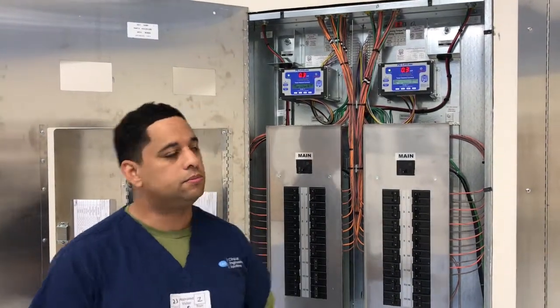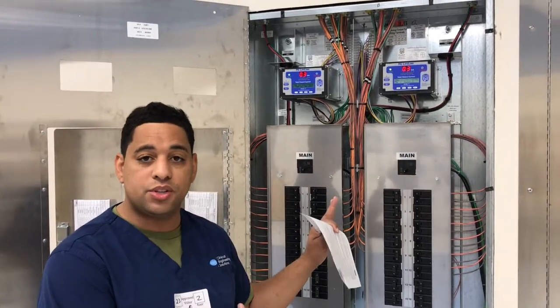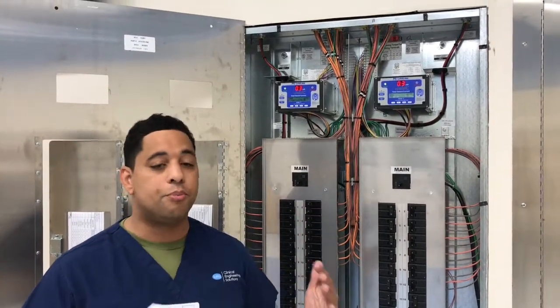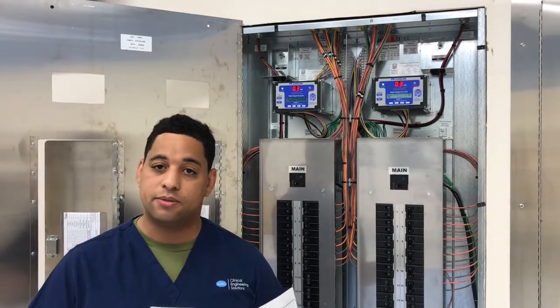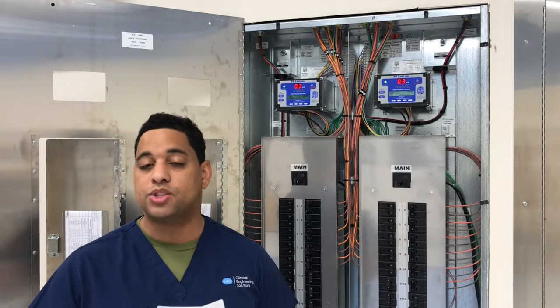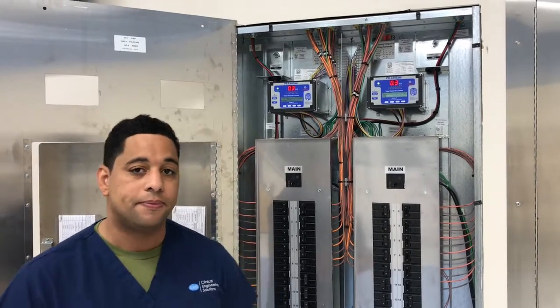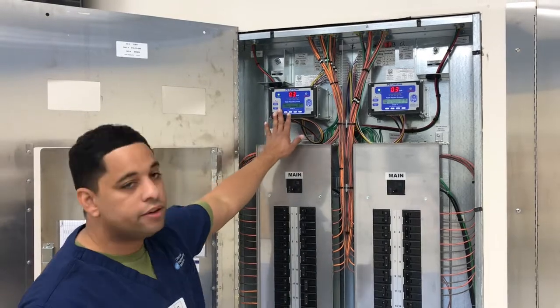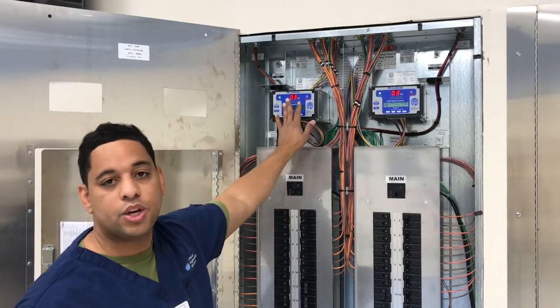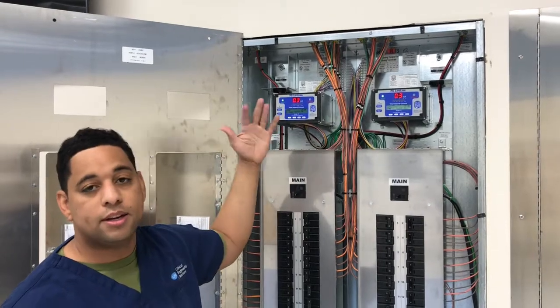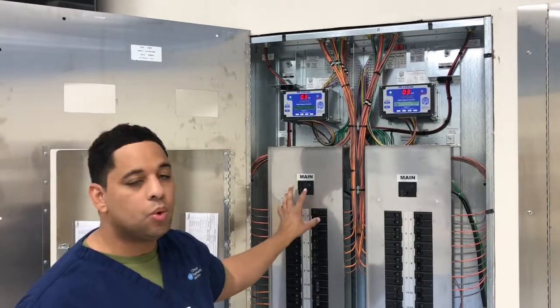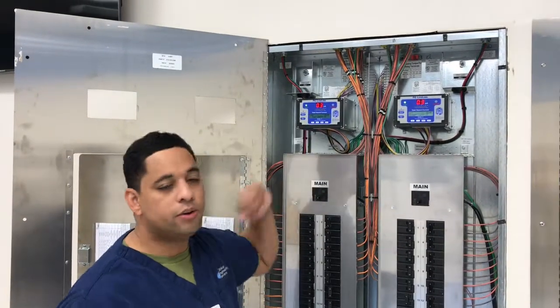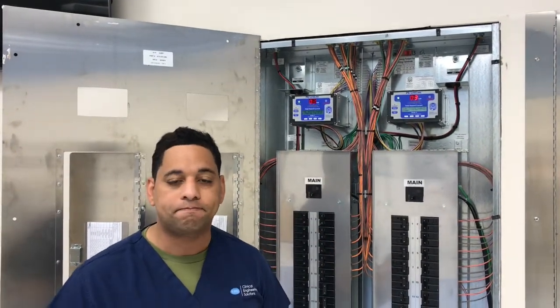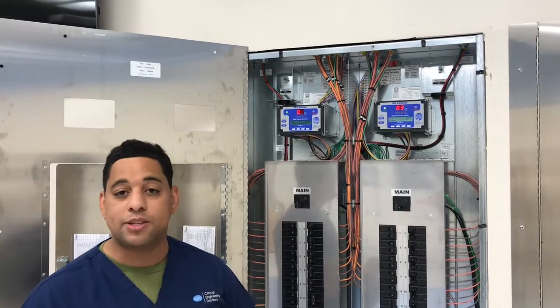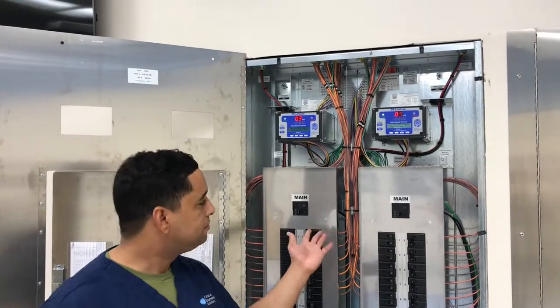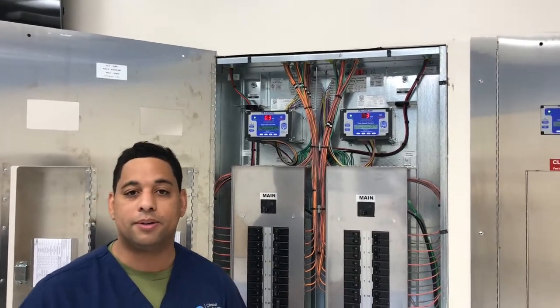So overall, this is a very important safety device, safety feature. It's here for a very important reason, to prevent shock hazard, which is critical in a hospital setting, especially one where surgeries are taking place. Number two, the monitor is very important to not ignore when it goes off, but also keep in mind it does not affect your power. Power will not be shut off due to the monitor or a device which may have a problem. And finally, it must be tested once a year. That being said, enjoy using the isolated power.